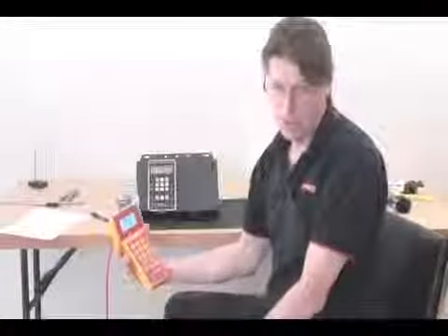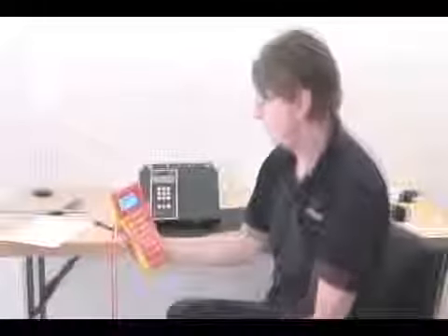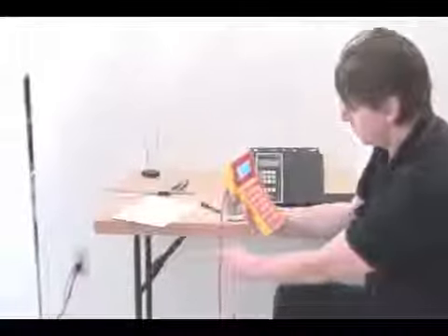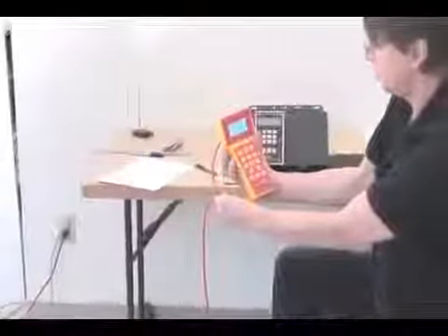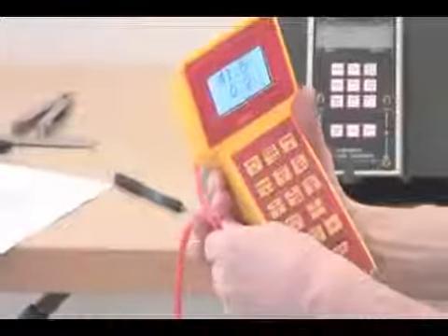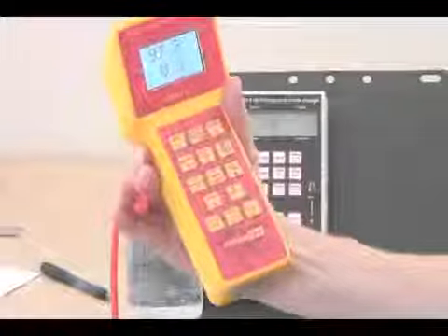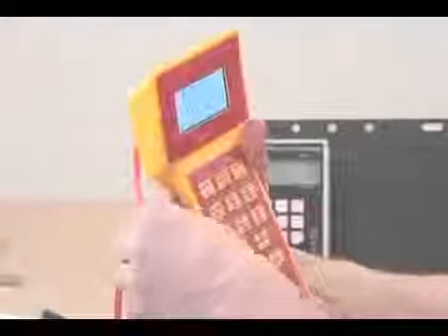So the next thing we're going to talk about is the old pinch tube problem. And I've seen people close tubes indoors and see the effects of a pinch tube. So if we were to pinch this tube right now, you notice that the pressure goes up. And it doesn't really matter what kind of pressure is applied on the end of the tube. It doesn't pay any attention to it. So if we're to blow in the end of this tube, it doesn't do anything. The pressure that the gauge is seeing is between here and the gauge, and the air has been compressed in this piece of tube, so it doesn't pay any attention to it.